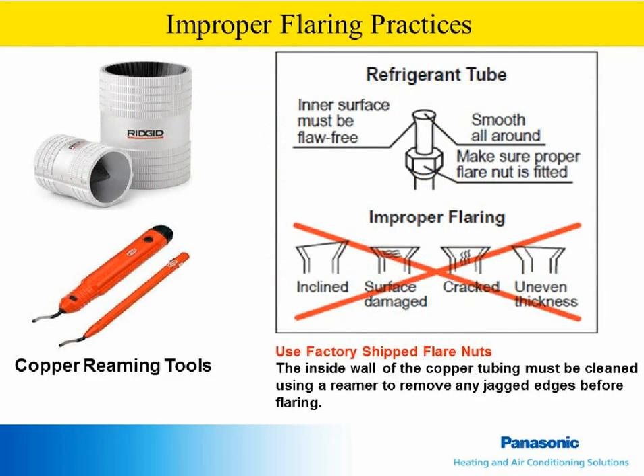Before making flares, always remember to slide the nut onto the pipe. It's very aggravating to make a nice flare and realize you forgot the nut. Make nice straight cuts and deburr the inside and the outside of the tubing. If you're not using the Panasonic supplied flare nuts, make sure that the ones you are using are heavy duty. Forged flare nuts are stronger than cast ones and less prone to cracking. Don't forget that both lines will sweat, so they need to be insulated individually.